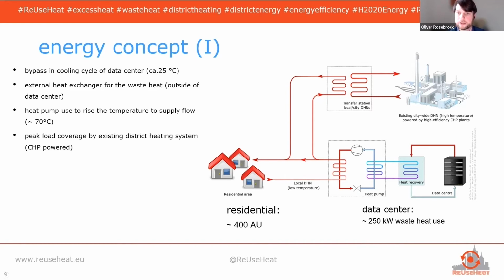The data center is cooled down to 25 degrees C, or the cooling system of the data center has a temperature of 25 degrees C. By heat pump, this temperature level is increased to 70 degrees C, which is the supply flow temperature of the district heating network for this new area. This new area is also indirectly connected with the existing district heating network. This is why I mentioned this before.